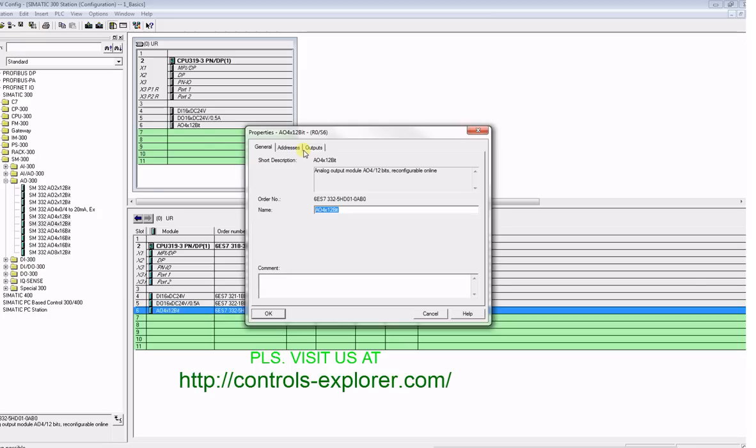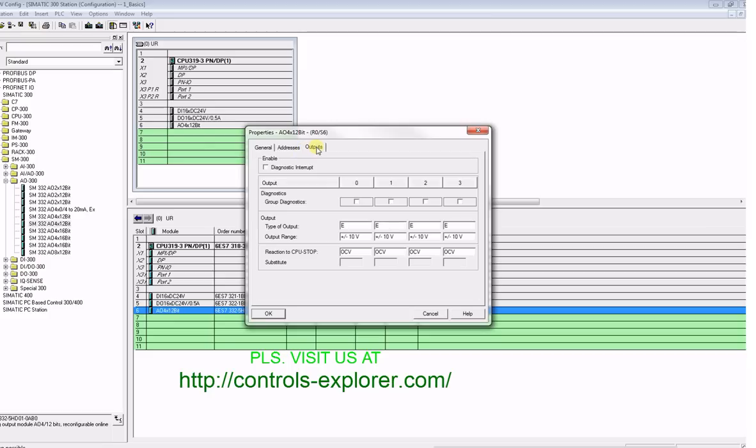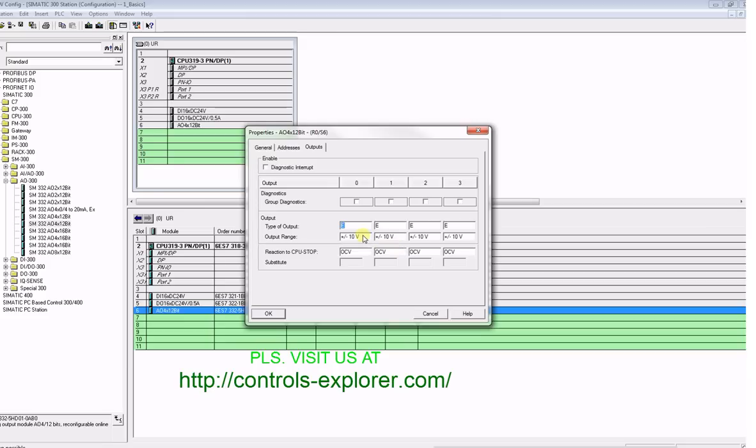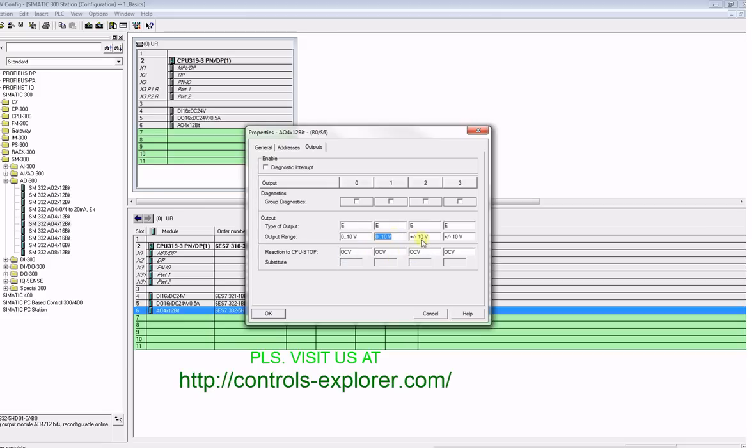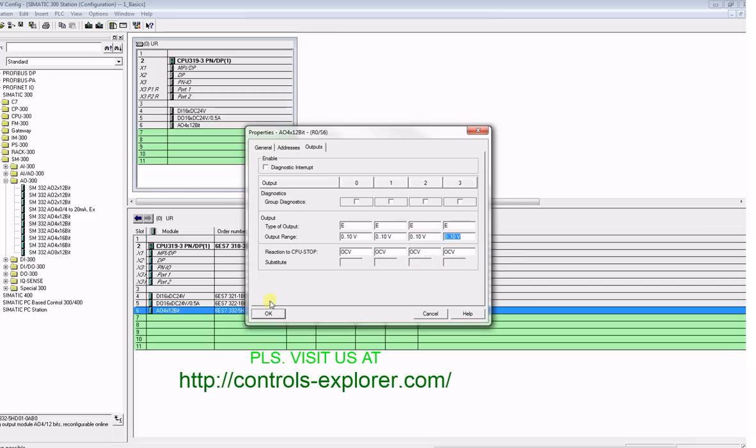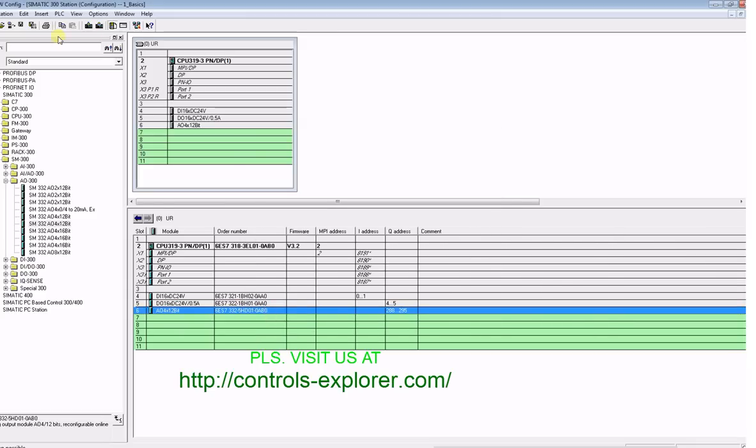When you double-click the analog card under this new window, the properties, click the outputs. You could see for the individual channel you have a selection for voltage or current, and again on the voltage you have different selections. For this example, let's select 0 to 10 volt for all and save and compile.